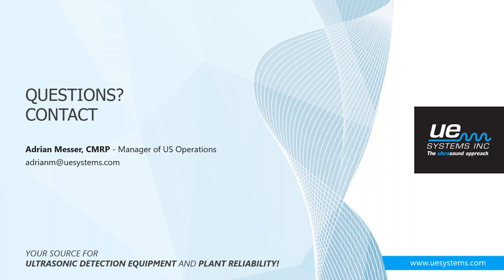Yeah, that's a great question. Very common question when we're in front of people talking about this. But again, the software will default to the first reading that you take and download into it from the grease caddy. It'll set that as the baseline. But you can change that baseline at any given time. I talked a little bit about the historical method, where we set up the route and go out and acquire that initial round of data, so we build an initial trend. And then you can use any one of those readings as the baseline.